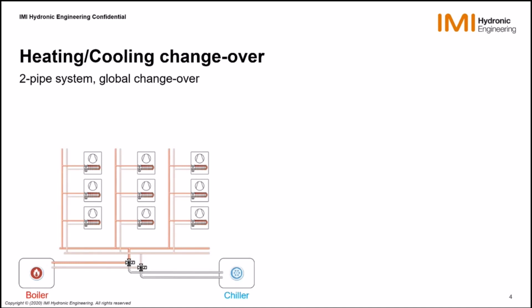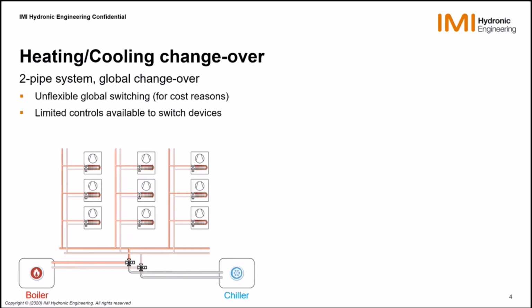Heating cooling changeover, just to fix the minds, two pipe system here illustrated as it is in heating mode. You get a two-pipe system globally delivering to a number of units, and at some point you are switching between a boiler and a chiller. So you are globally in the system in heating mode or globally in cooling mode. And at one moment in time, there is a decision that is taken. It will be typically at spring you go to cooling, and at fall you go back to heating. It isn't flexible, it's global switching, and it is usually made in this way for cost reasons.